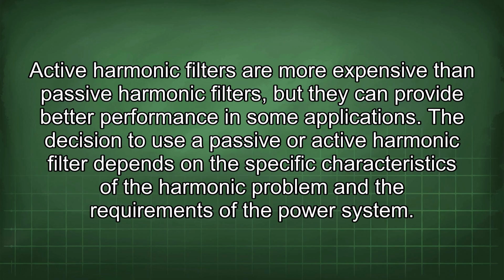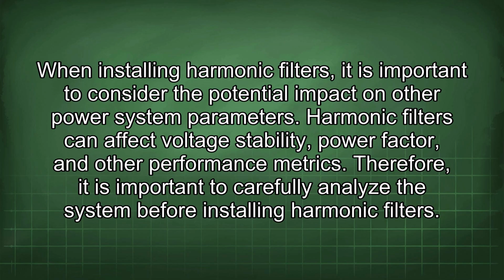Active harmonic filters are more expensive than passive harmonic filters, but they can provide better performance in some applications. The decision to use a passive or active harmonic filter depends on the specific characteristics of the harmonic problem and the requirements of the power system. When installing harmonic filters, it is important to consider the potential impact on other power system parameters. Harmonic filters can affect voltage stability, power factor, and other performance metrics. Therefore, it is important to carefully analyze the system before installing harmonic filters.